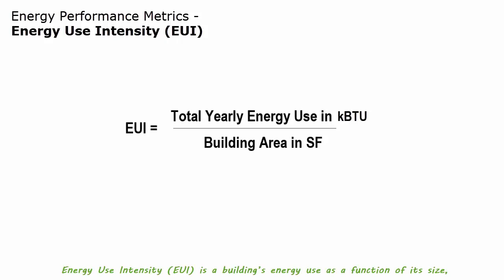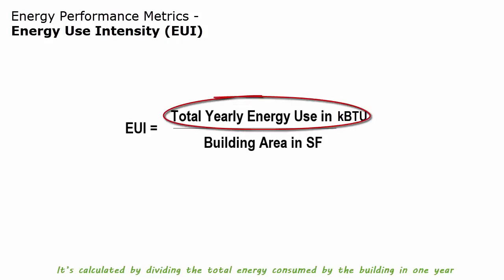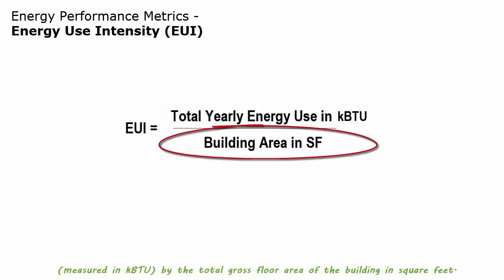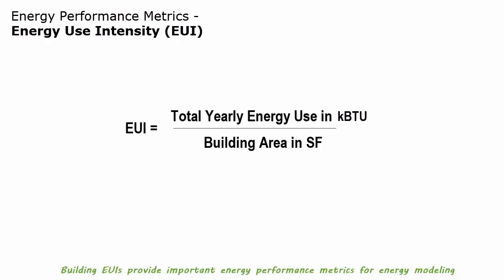Energy use intensity, EUI, is a building's energy use as a function of its size, which is expressed as energy per square foot per year. It is calculated by dividing the total energy consumed by the building in 1 year, measured in kBTU, by the total gross floor area of the building in square feet. Building EUIs provide important energy performance metrics for energy modeling and assessment of building energy performance. Building type is one of the main factors that determine EUI. Hospitals have EUIs that can range from 400 to 500 kBTUs per square foot. A school may have an EUI in the range of 150 kBTU per square foot. Climate can have a significant impact on EUI as well, due to the variations in heating and cooling ambient conditions.